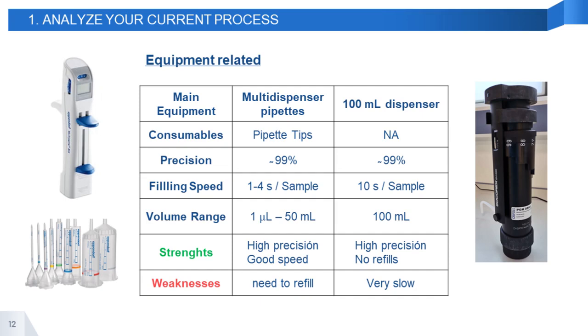And then the other equipment, the black one on the right, is a 100 milliliter dispenser that is directly attached to a bulk container, and pulling the tip up and pushing down, liquid is pumped to the final container. The precision of this equipment is also close to 99%, varying a little bit depending on the target volume. Then the speed of the dispenser pipette is really fast, but the 100 milliliter dispenser is not at all. These two equipment together allow to have a much wider volume range from 1 microliter to 100 milliliters, which is a good strength if considered together.